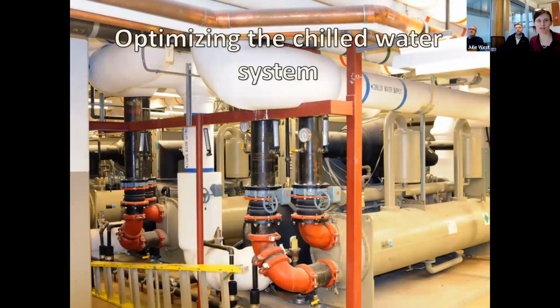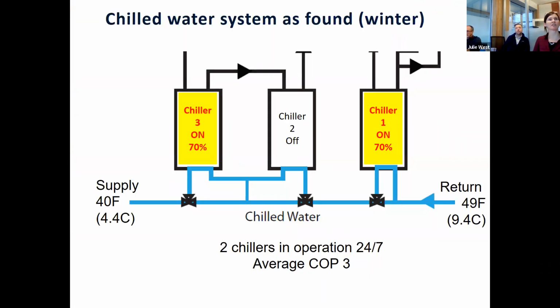The next thing we did here, how am I doing for time? We optimized the chilled water system on campus, or sorry, in the building. So we have 3 chillers, and 2 of them would run at about 70% load. And we averaged a COP of 3. The supply water temperature was around 4.4 C, returning at around 9.4. And this is what we were running at in the winter.